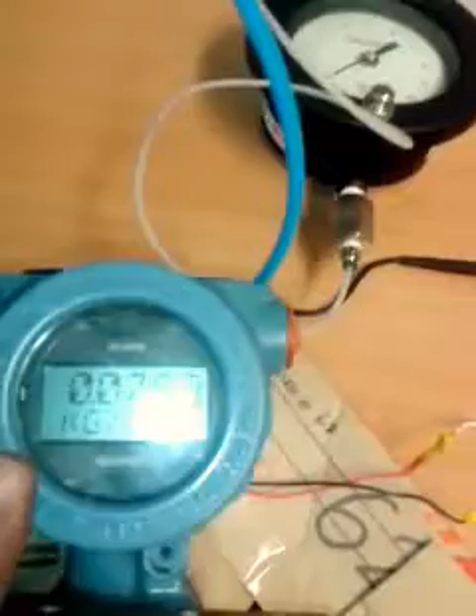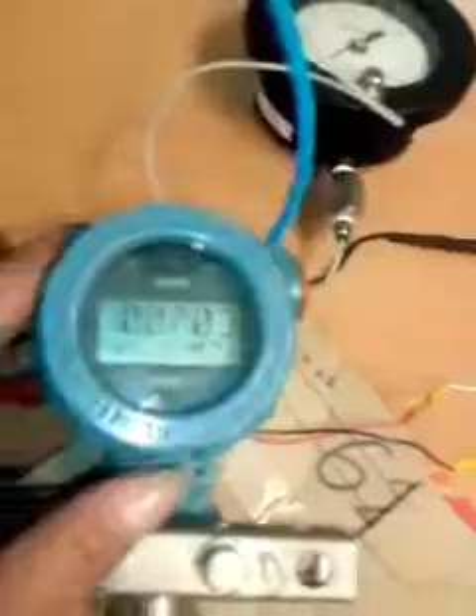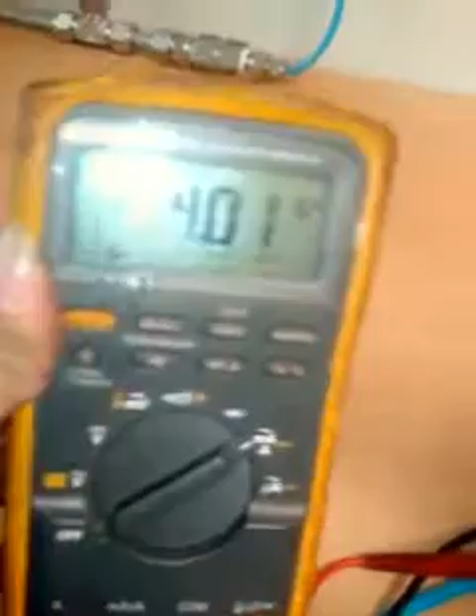Our current meter made by Fluke 87. As you see, the display is 0 pressure. The range of this transmitter is 0 to 300 bars. Since the display is 0, the corresponding current is 4 milliamp. We have the HART communicator made by Emerson's 475 and the standard test gauge made by Ashcroft, our reference.